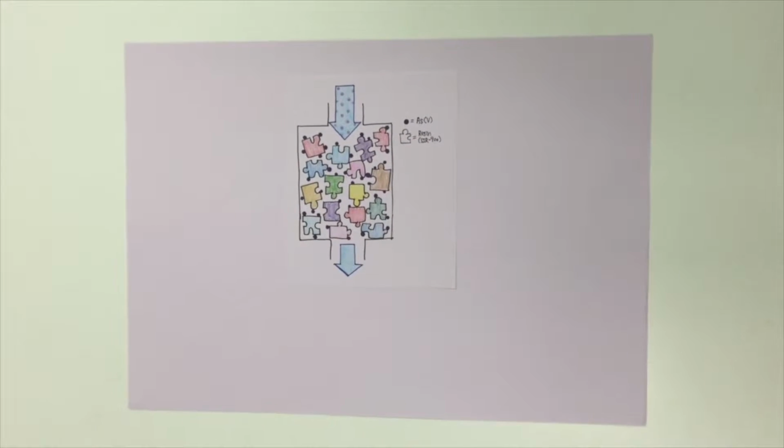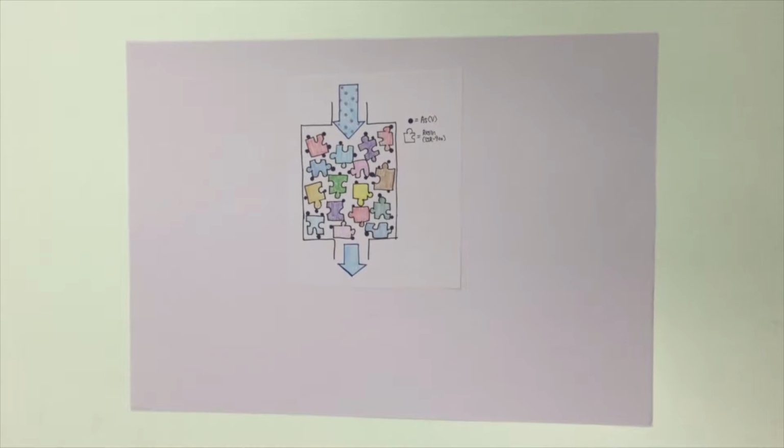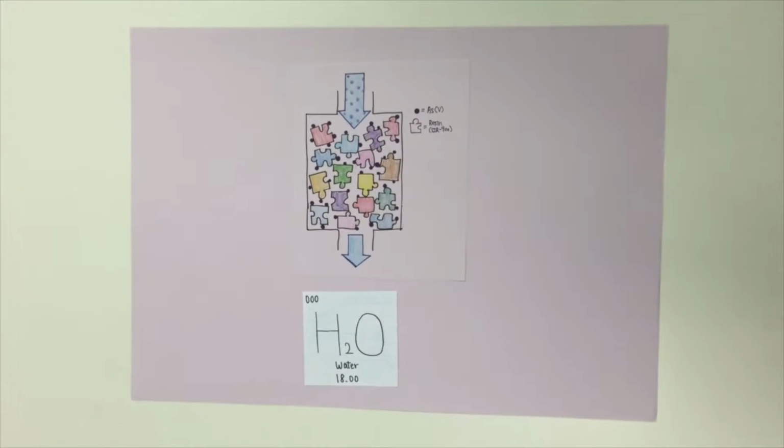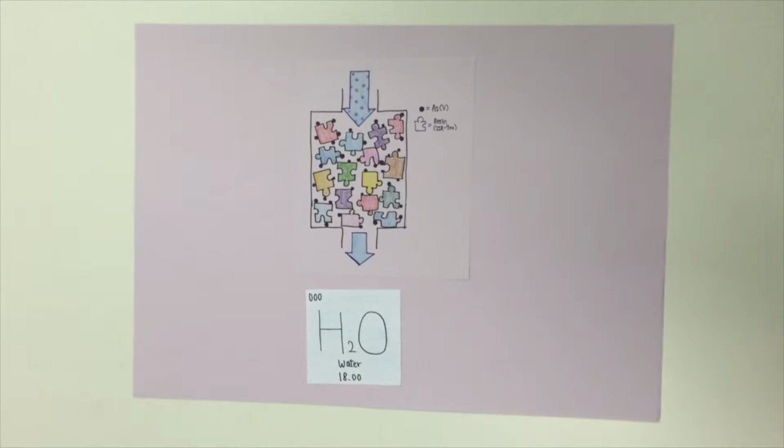After that, arsenic ion is removed by using ion exchange. You can see here is a tank which is full of resin. The resin that we use is SIR 900, which is an arsenic absorbent. The pH value should be set between 4 and 10, and the temperature should be set below 100 Celsius.